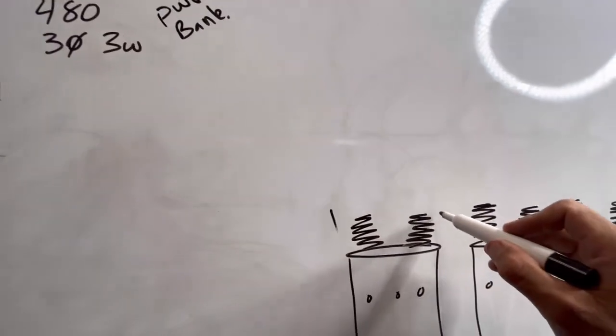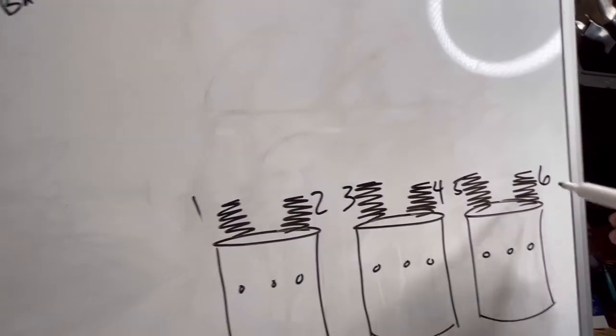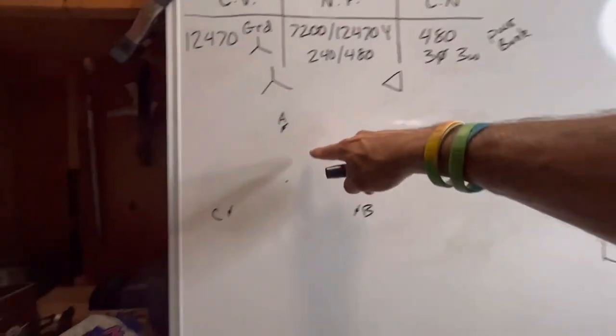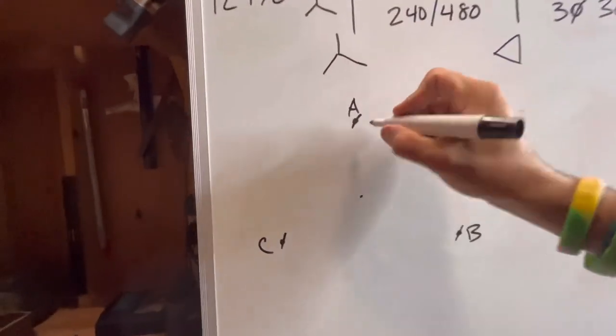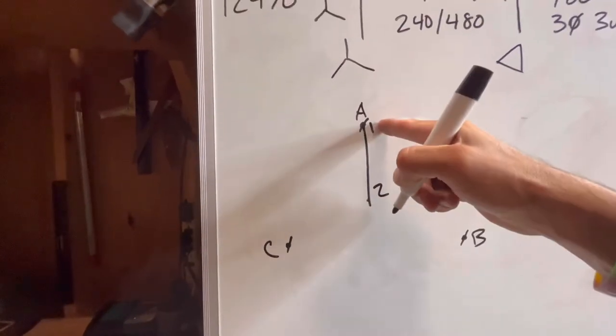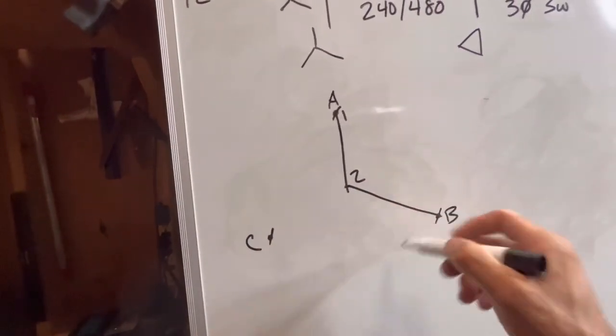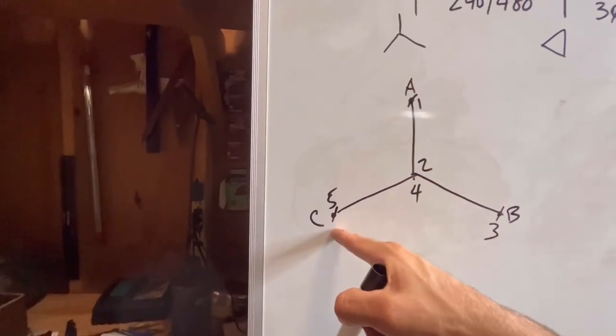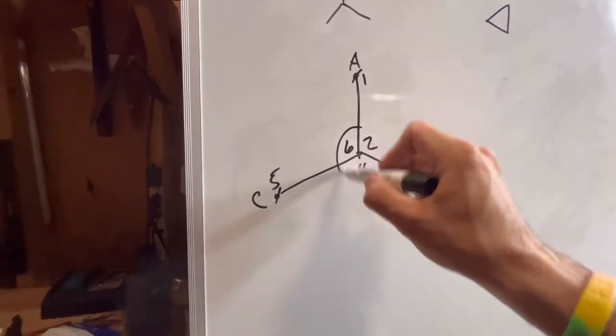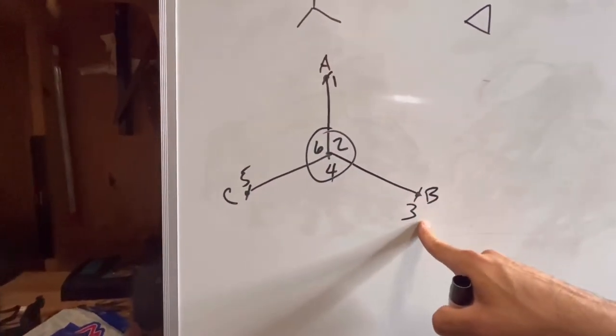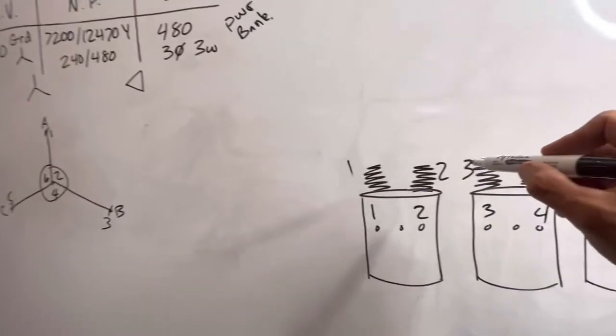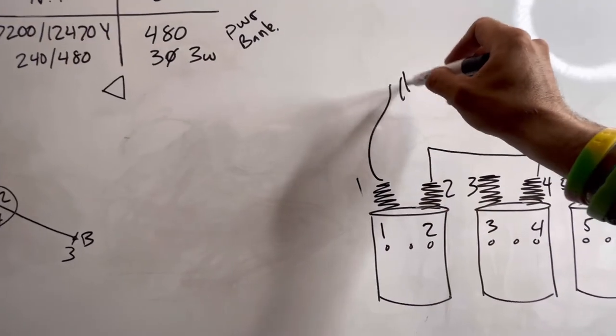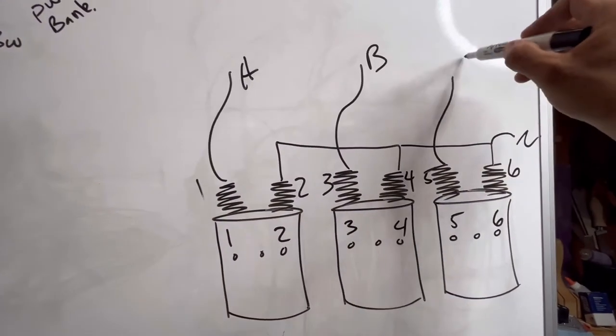Next, number our transformer bank from left to right: 1, 2, 3, 4, 5, 6, both primary and secondary. Then hook up the primary circuit — it's a Y hookup. I take my 1,2 transformer: 1 going to A, 2 going to neutral. My 3,4 transformer: 3 to B, 4 to neutral. My 5,6 transformer: 5 to C, 6 to neutral. So we've got a 2, 4, 6 tie all going to neutral. 1 going to A, 3 going to B, 5 going to C.